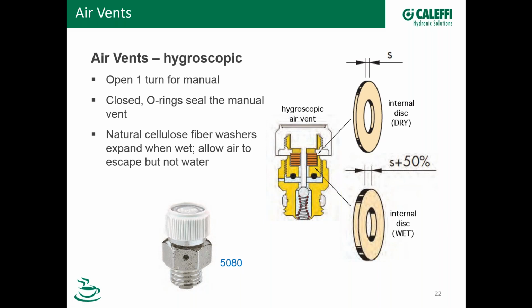So if they get wet, what happens? You can see here on the right, the certain thickness of the disc when it's dry. And as soon as it gets wet, within a few seconds, it expands. And what that does is it closes off that air escape and prevents water from getting out past your vent and dripping on a ceiling tile or something else that might be sensitive. And here's a picture of our 5080. That's a chrome-plated hygroscopic air vent that Caleffi sells.